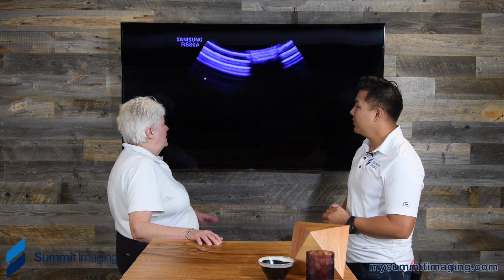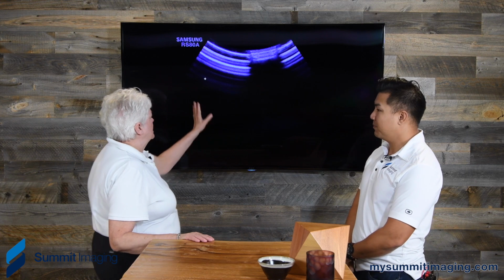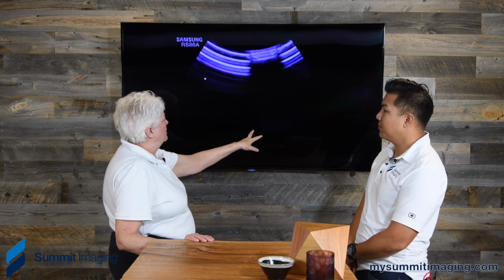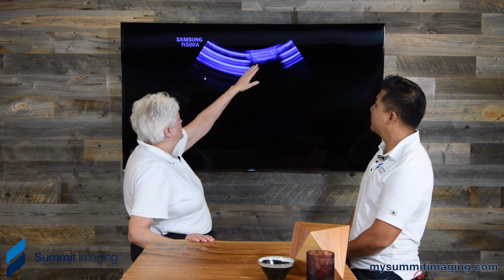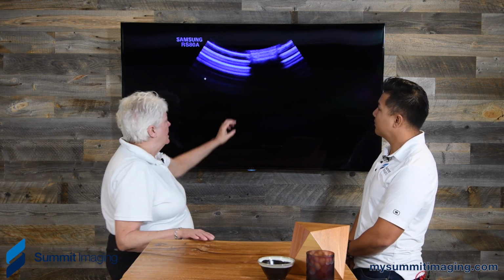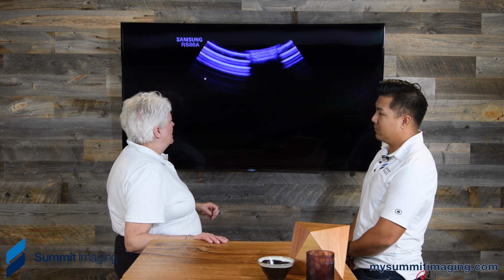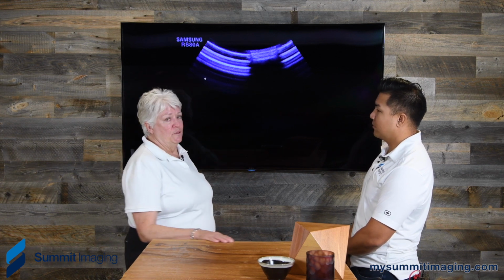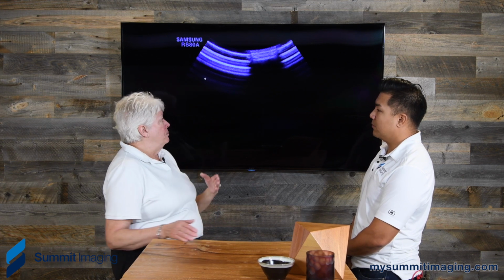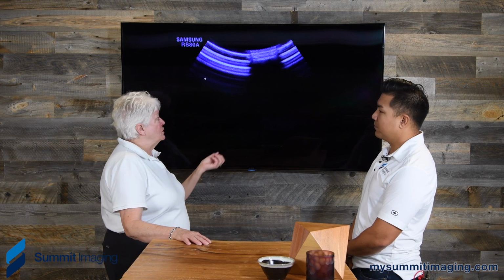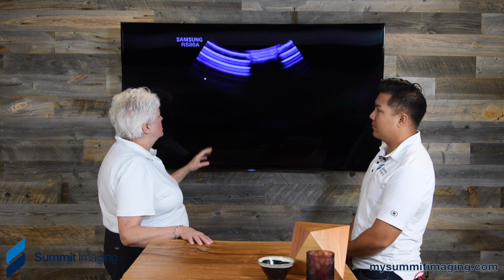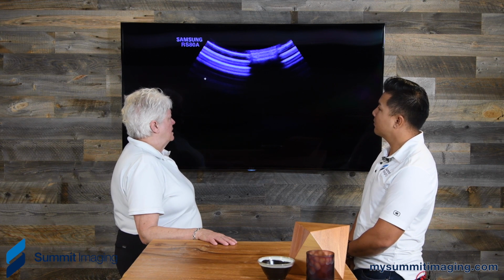From a clinical standpoint, there's a huge issue here. Let's assume that we're scanning a liver, and we have this area of dropout here, which presumably the sonographer would notice was right at the near field. But if they didn't see that, or if it wasn't visible on a real image, this area of dropout is hiding a lot of information. There could be a lesion, a cyst, or some kind of vascular issue in the liver, and you've lost that information. Any loss of information makes it non-diagnostic, but sonographers, and the physicians interpreting, often don't appreciate what the transducer problems are and what they can do to degrade the quality of the image. So you definitely want a nice homogeneous image across there, and you don't want any areas of dropout or areas that are being hidden by shadowing.